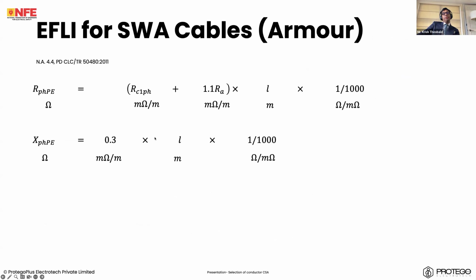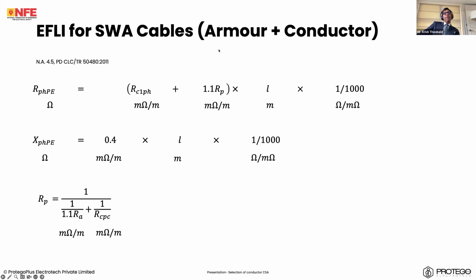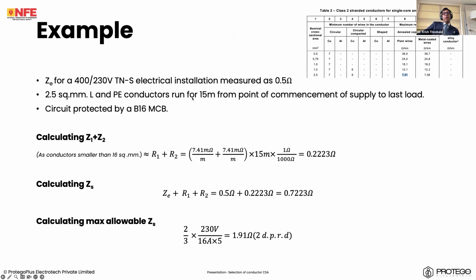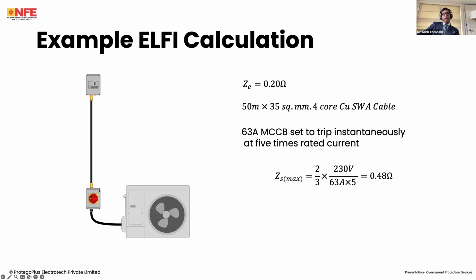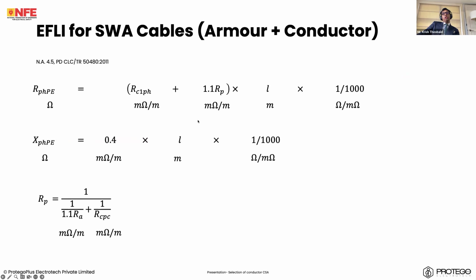Simple again. Then, what do we do if we have an armor plus a parallel conductor? What we do is quite simple. We follow the same loop: line plus PE, where line is just the core. PE is now the value of the armor plus the parallel conductor, RP, and we multiply by 1.1. Here, instead of 0.3 milliohms per meter, we take 0.4 milliohms per meter. The question is, how do we now calculate this RP? So, just one moment. I have a feeling there is a mistake in this slide. Let me just check.